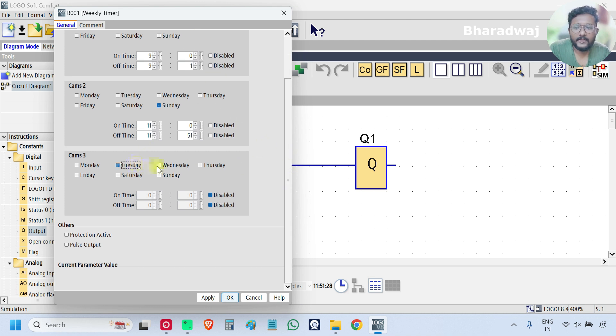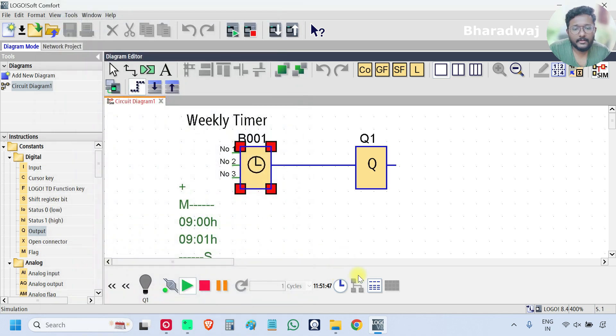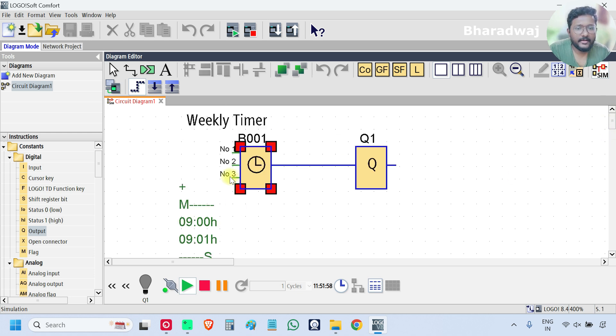Let's say on every Tuesday, Wednesday, Thursday at 11 — at 15:00, 3 p.m. — I will turn an output on, and after 10 minutes at 15:10 I want to turn off the output. You can scroll down and see: Tuesday, Wednesday, Thursday, 15:00:00 on time, 15:10 off time — that is the timing and day.